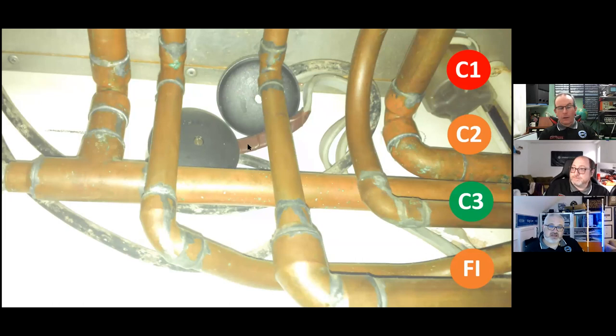There's definitely damage to that cable because they've obviously tried to tape it up to replicate an additional sheath, and the connections aren't fixed. And there's no mechanical protection on that cable as well. Remember, that tape, whilst it may be considered as additional sheath, 416 does say that insulation shall only be removed by destruction or with the use of a tool. So we can't consider it to be insulation in the 416 insulation medium if they put tape around it. Yeah, and there you go. That just shows my own stupidity. If I'm doing a drive-by, I'll open up a door, look at that and go, oh yeah, C3 requires improvement, close the door again. Spend 5 minutes thinking about it and it's a C2.